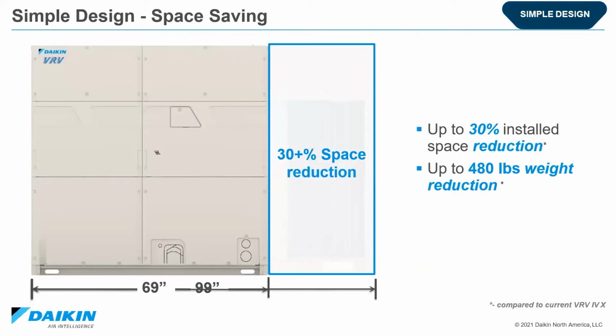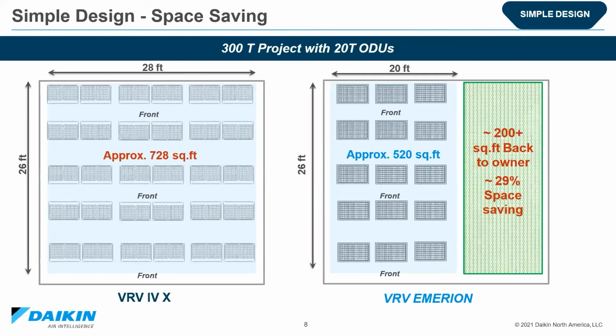With advances in technology, the new design has allowed for up to 30% reduction in overall space, and also up to 480 pounds in weight reduction. This benefit is going to allow contractors to reduce their installation costs. And then it also provides the owner more usable square footage and less mechanical space. Seen here, you can see how a 300-ton project could have its condenser plant size reduced by up to 29%. And that space could be utilized for other things.